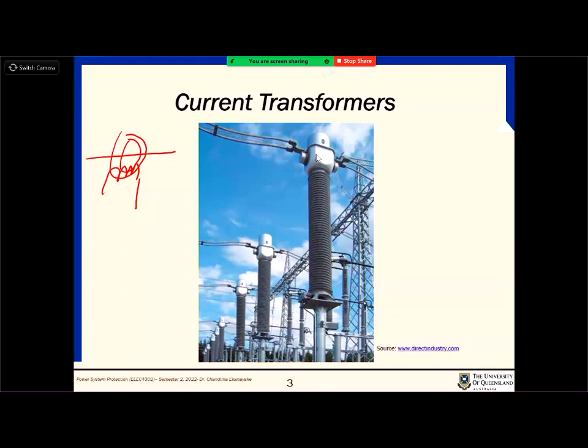The current is going through this toroid, and then you have another secondary winding around it, and this will give a certain current measurement. This is the I primary, and this is the I secondary, and that secondary is fed to the relay. Then we have all these insulators, which are extra protection for high voltages. But what you can see here on the left hand side is the basic operation of it. It's very simple.